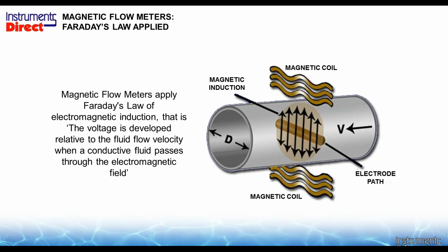So in this case, we have our pipe. We wrap a copper coil around it, and then we have two little electrodes here and here. Let's call them our voltmeter. What happens with this application is these magnets create a curtain across the pipe. As the conductive media, here we go, water, goes through this curtain at a right angle, it creates a small current. These electrodes here and here measure it. The more that goes through there, the greater the current. So that's the basics of Faraday's laws of magnetic induction.